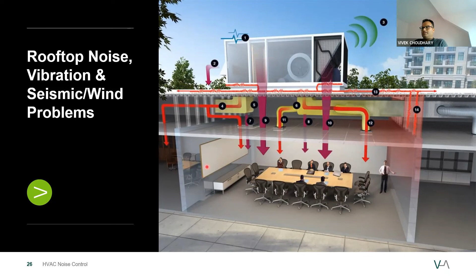So we do the analysis and come up with a solution like this. We call it an integrated noise control package, which combines a vibration isolation curb, acoustical barrier, and supply and return silencers. It's a package combination of a few noise control solutions to make sure we meet the required NC criteria right below the space.